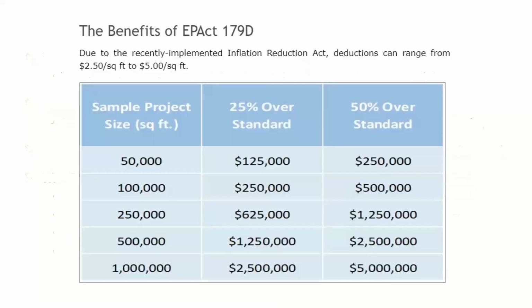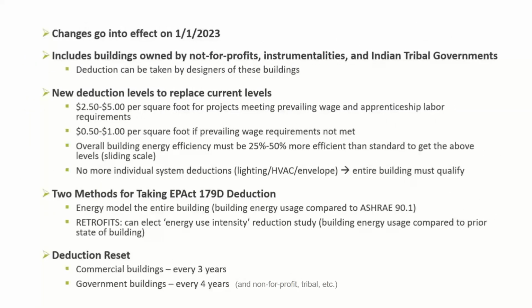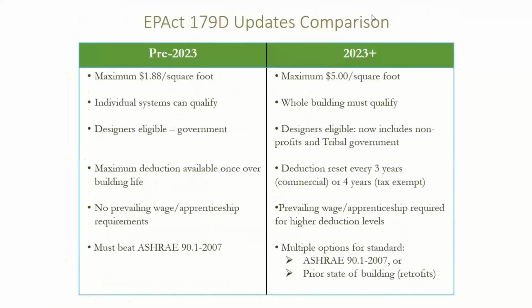On the commercial side, the big difference is that it doesn't matter at all where the savings comes from. Residentially, you do certain things, like a furnace or a heat pump. Commercially, it doesn't care where it comes from, it could be a better building envelope, better windows, a more efficient boiler, or mechanical insulation on steam piping. However, just insulating steam piping alone and doing nothing else in the building won't get you 25 to 50% savings over the old code. It's not enough savings, so any single individual improvement is unlikely to be enough to get a commercial tax credit by itself.